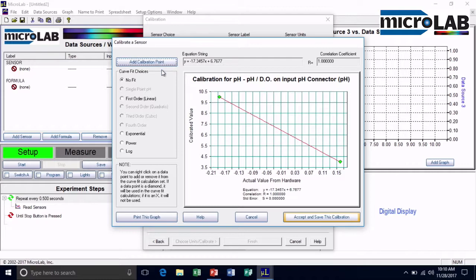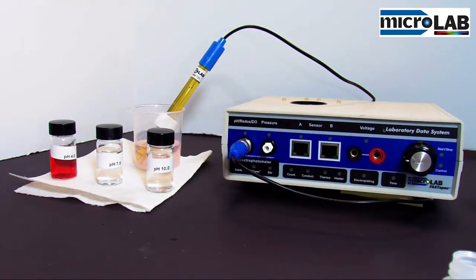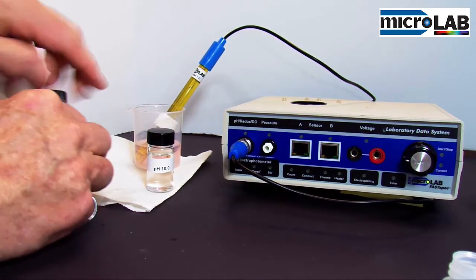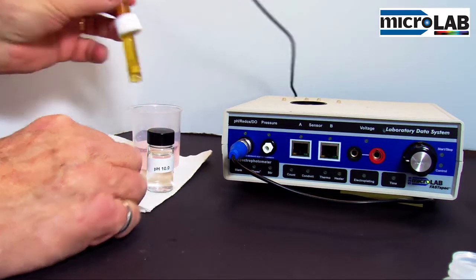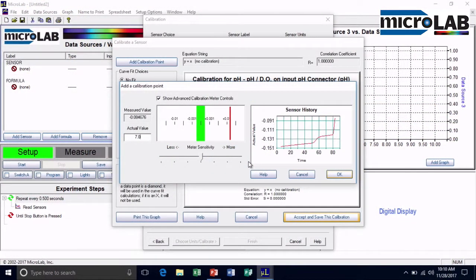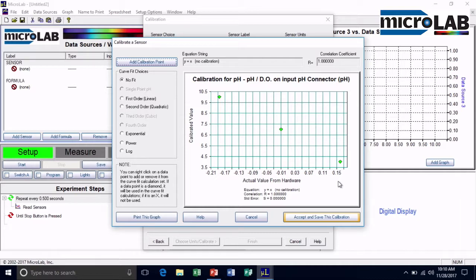So let's add another point, and I have some pH 7 buffer, and let's open that up and we'll switch back here. And if we could watch the graph as I put this in, there we got it, and it changed rapidly. And let's wait for that to equilibrate. And that looks pretty good. So I'll say, okay, we'll grab that point. And we now have 3 data points. If I do a curve fit, it's almost a perfect straight line. The correlation coefficient has 4 9s in it. All we did with that 3rd point is prove that our first 2 points were accurate.